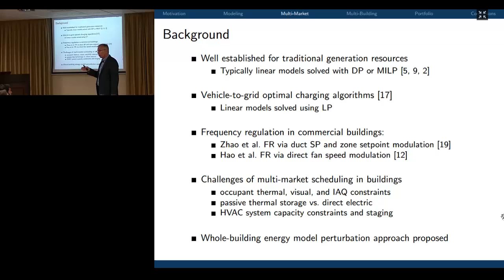Imagine it's 1 o'clock in the afternoon and a building is maintained at 23 degrees Celsius. For this hour, from 12 to 1, you're asking how much FR, frequency regulation, can I provide? The building cannot be colder than 22 or warmer than 23.7, so I'm allowed to move within that range. I've kept the building at exactly 23, so that's my starting point.